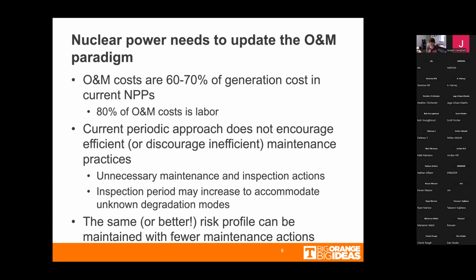And so at every outage, we might take all of the sensors out of the system to evaluate their calibration status. If you want to take a sensor out of the system, then we have to isolate it from the system, remove it, apply a false load onto the sensor that will sweep across the range of the sensor, evaluate the calibration status, recalibrate if necessary, and then put it back into the system. And so if we're doing that every outage, we run into a couple of problems, especially thinking about calibration assessment.